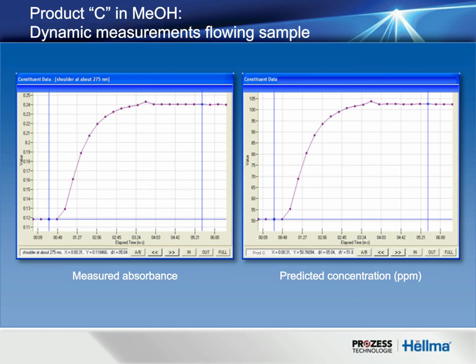Excellent. Maybe we'll just do one or two more questions and then wrap up. So you had mentioned something about bubbles. This person says, we don't always have a clear stream to measure. Can your solution be used with bubbles? I believe what I said before is potentially the answer to this: bubbles are not necessarily a real problem because they typically move very rapidly out of the light path. So the orientation of the probe to the stream and the bubbles themselves can be placed to eliminate that. Additionally, we have a specially designed sample interface with a vertical slit whose geometry is specifically designed to exclude bubbles from the light path.